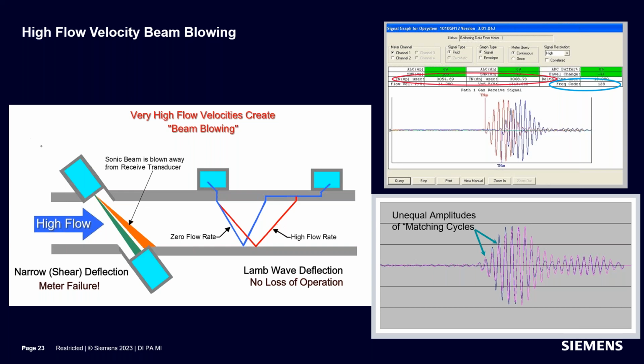In order to do it, the 2 signals must be at least 1 cycle phase shifted from one another. So it can't be done at 0 flow. But if the flow is too low to do the correction properly, the meter will just tell you that, and it won't do it. Once the flow is established, you can go ahead and do this beam blowing correlation correction.